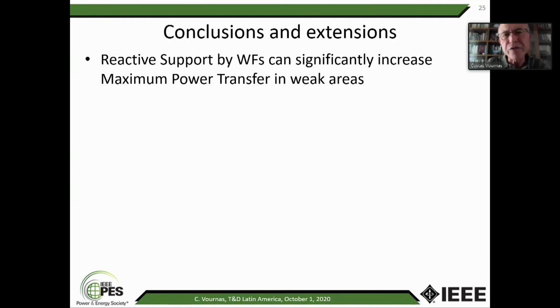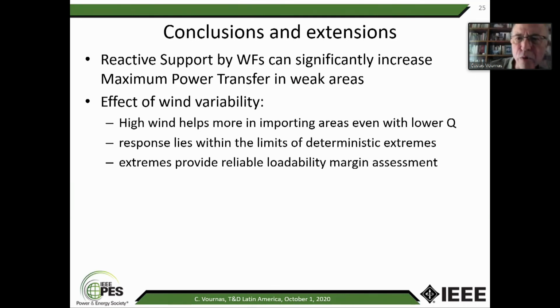Okay, so as I showed, the reactive support by wind farms can significantly increase maximum power transfer in weak areas, both in simple systems and more complex real systems. The wind variability in this case is not always the same, but in this case, high wind helps more because it imports less active power, even though it can support less reactive power. The variable or probabilistic stochastic wind gives results that are within the extremes, which is good because you can only do the extremes and know what is the maximum and minimum, but this is not always the case. I repeat, these are case-specific conclusions, not for all cases.